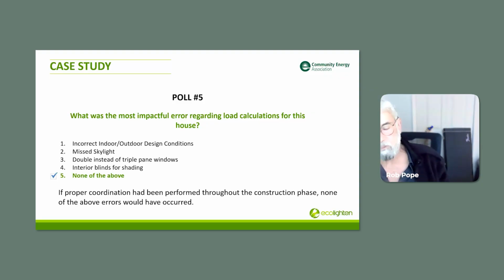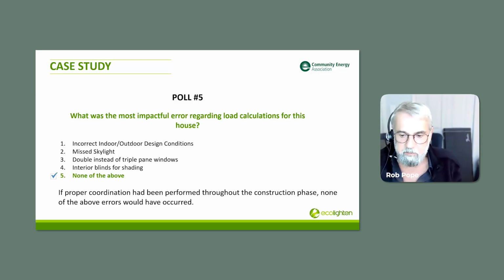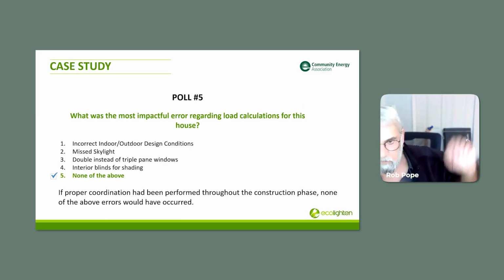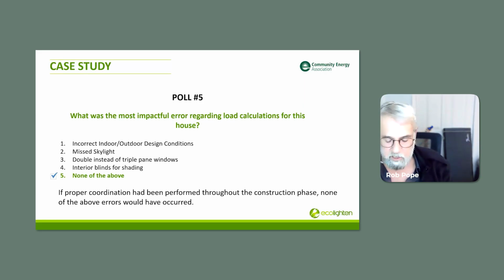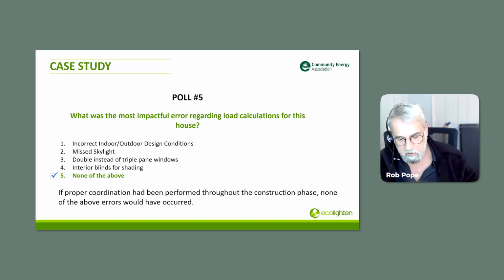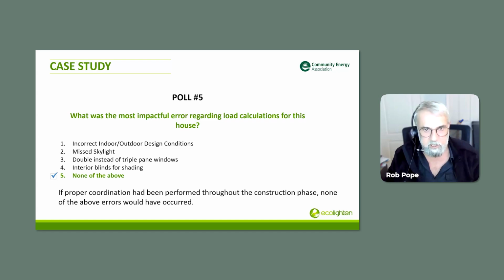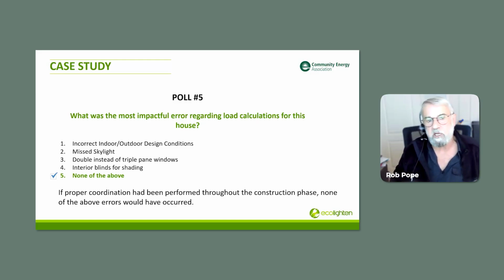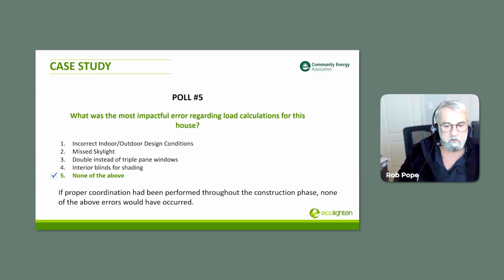It's none of the above, right? And the reason I say this is because when you're doing load calculations, you can't do it in a vacuum. You don't want the HVAC contractor sending off the plans to the supplier and saying, do the load calculations, give me the loss leader load calculations, I'll buy my stuff from you. That never goes well. You have to have some skin in the game, be engaged with the project, ask the questions, and coordinate. In this case, that coordination didn't happen. If proper coordination had been performed throughout the construction phase, none of the above errors would have occurred. None of them.